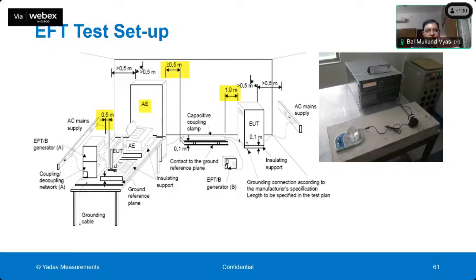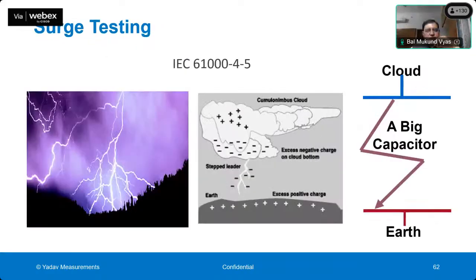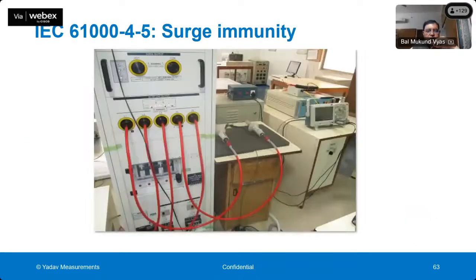Okay, right, thank you. So this is the fast transient test. Another kind of test which a meter has to pass is the lightning surge. You might have noticed that when there is a lightning surge, devices in our houses are also damaged, and sometimes the supply gets disconnected because of problems in the substation. Lightning surges can be very damaging to the meter and other devices, so the meter has to pass this lightning surge test.